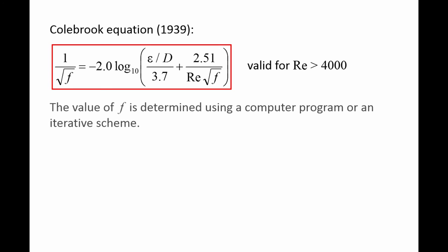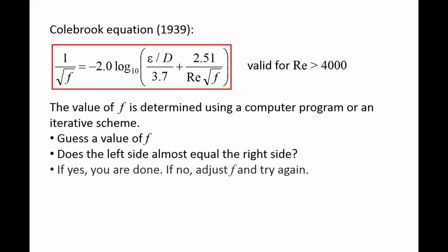However, computers can find f quite easily using a root-finding algorithm if the relative roughness and Reynolds number are known. Alternatively, if you don't have access to a computer, you can use an iterative scheme to find f through a hand calculation. First you guess the value of f, then check if the left side of the equation equals the right side of the equation. If the two sides of the equation are almost equal, you are done. If the two sides of the equation are very different though, adjust the value of f and try again.